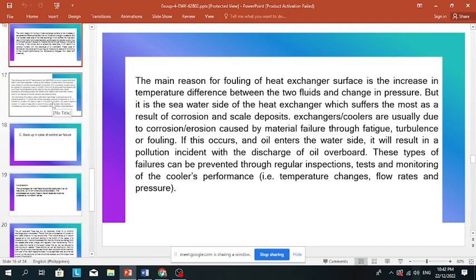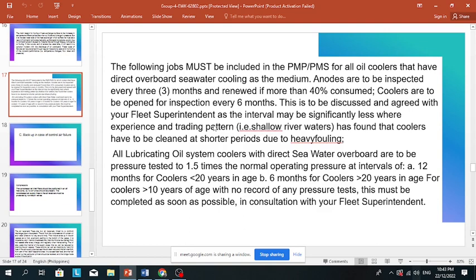These types of failure can be prevented through regular inspection, tests, and monitoring of the cooler's performance, temperature changes, flow rates, and pressures. So those are the precautions and procedures to be taken for the heat exchanger under blackout.